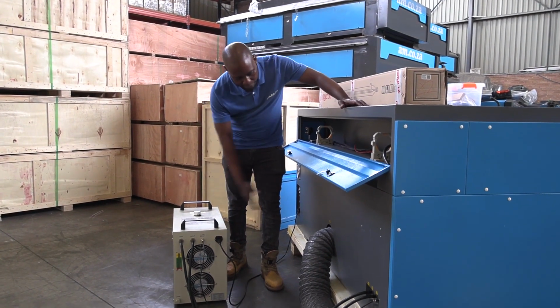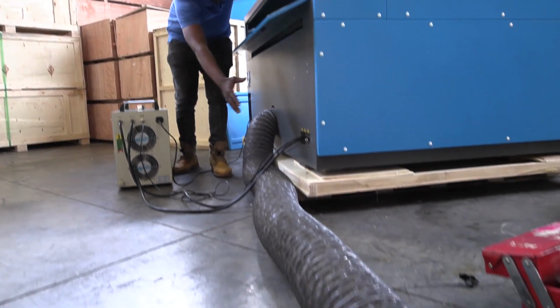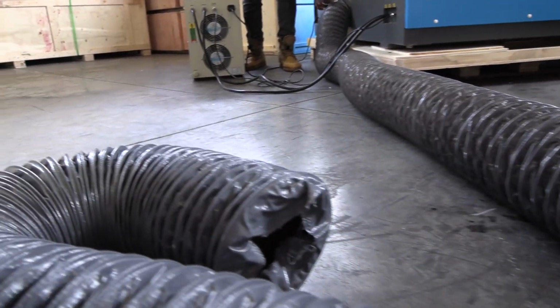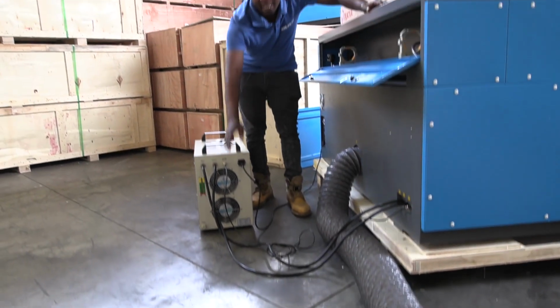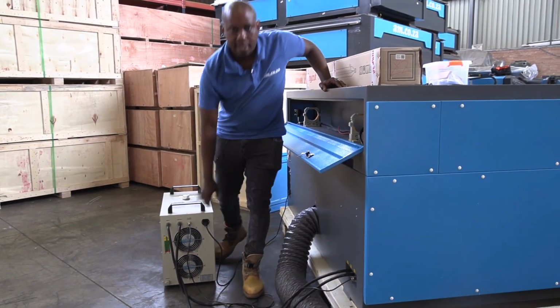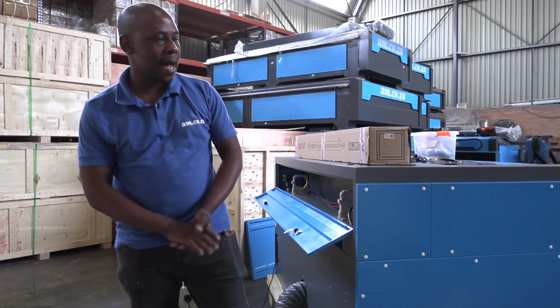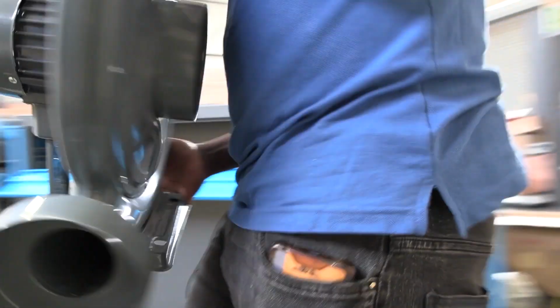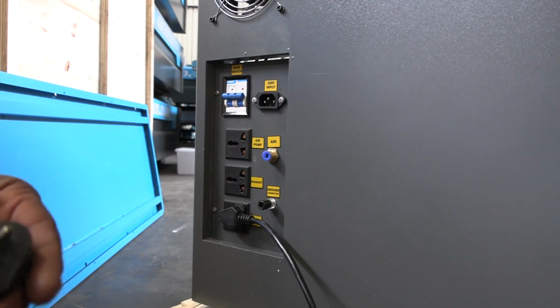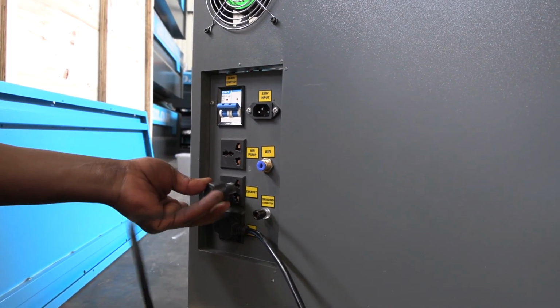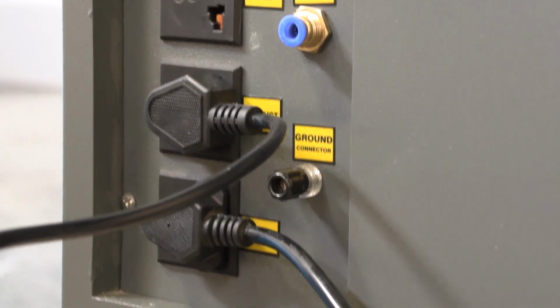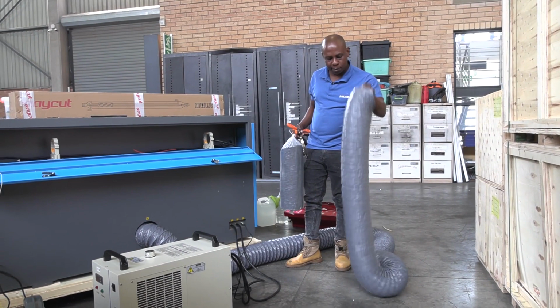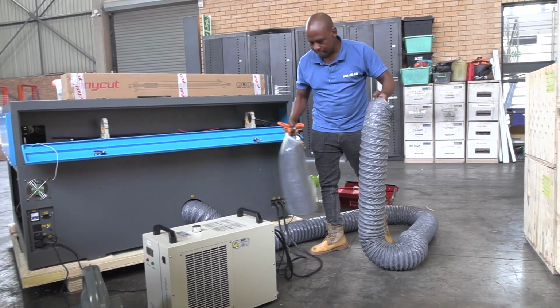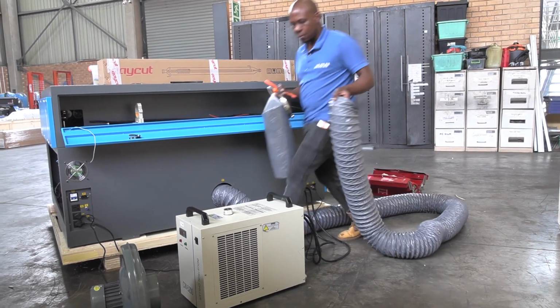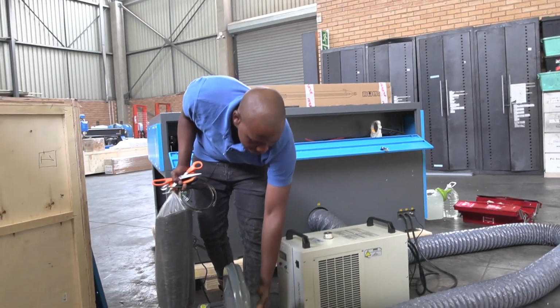And by the way, you can notice I've already taken out my exhaust pipe out of the machine by just reaching out my hand and pulling it out and stretching it out all outside. So next, I'm gonna now install my exhaust fan. I'm just gonna unwind my cable, connect it to the machine so that I can find a comfortable position to house my extraction fan behind the machine. Now first, what I want to do is connect the hose that is coming out from the extraction from the machine onto the motor of the extraction fan.